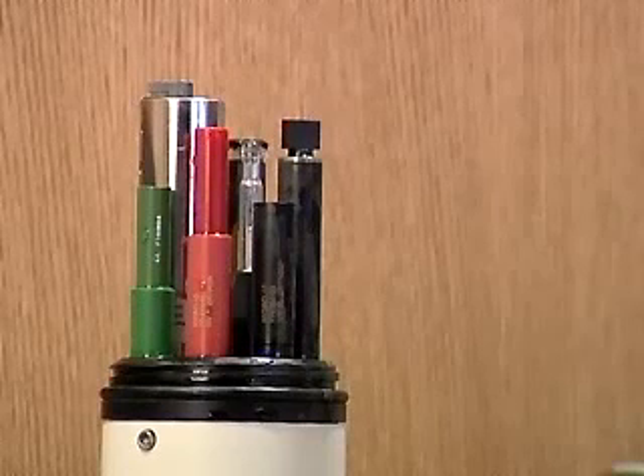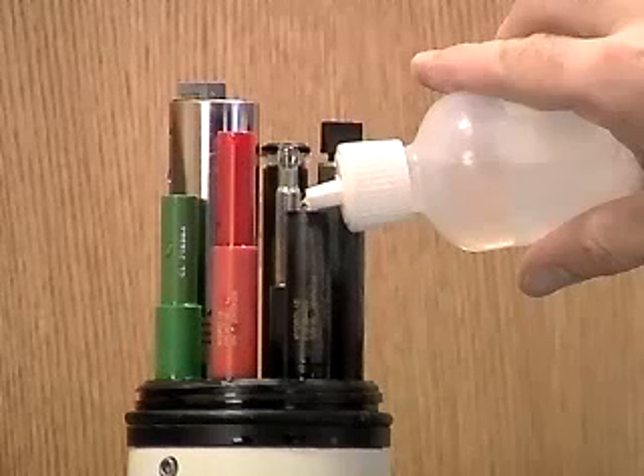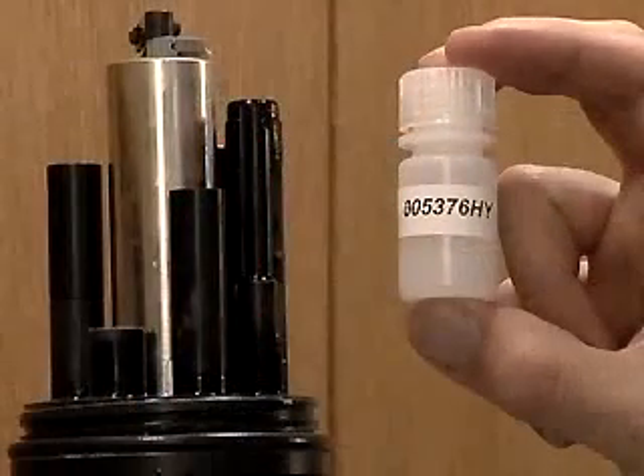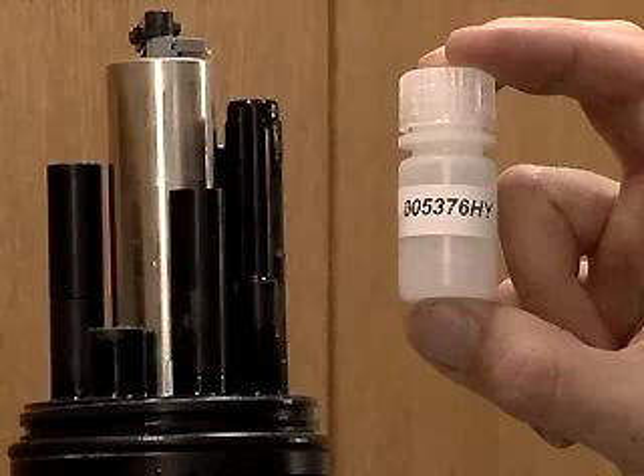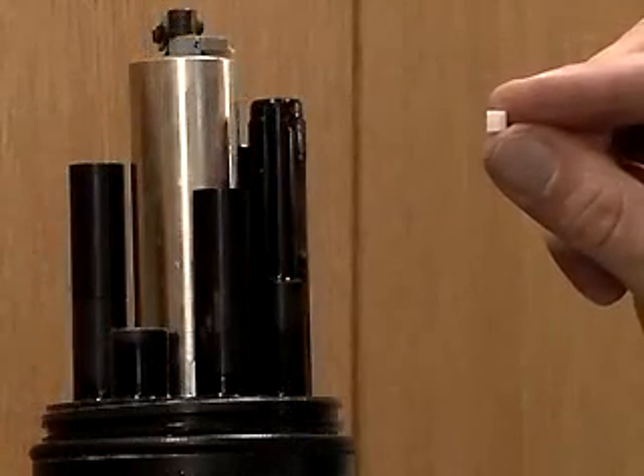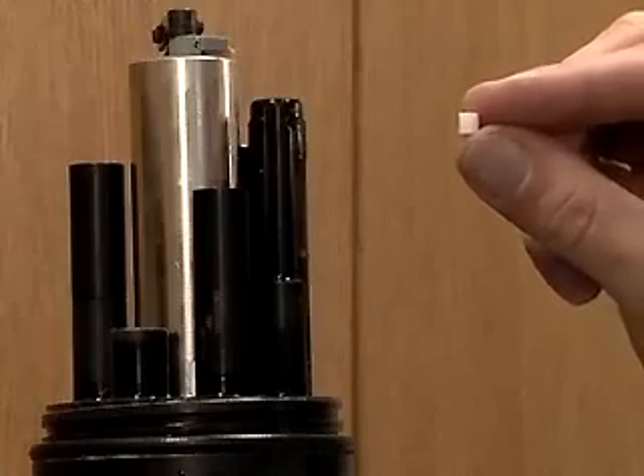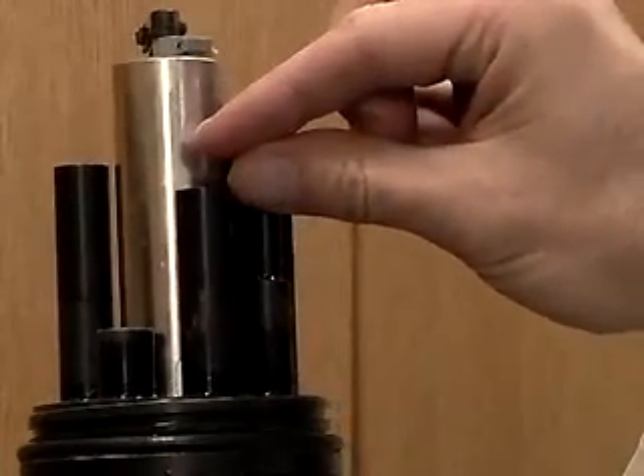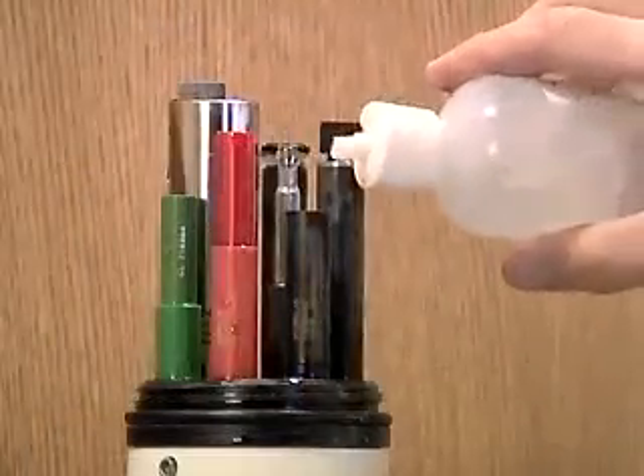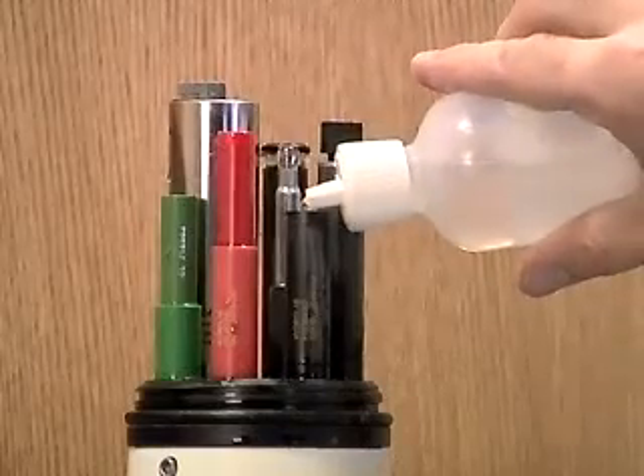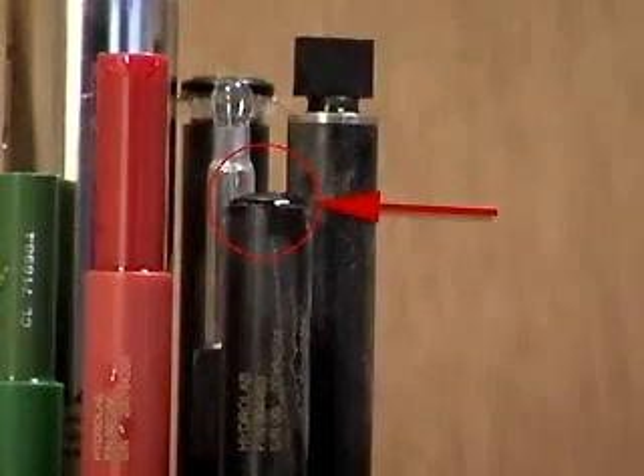With the junction off, pour the old electrolyte solution out and replace it with fresh. For extended deployments or for monitoring extremely low conductivity water, add a salt tablet to the reference electrolyte as well. This will maintain the saturation level of the electrolyte as the salt slowly leaches through the Teflon junction. Fill the reference until the electrolyte forms a slight dome over the top.